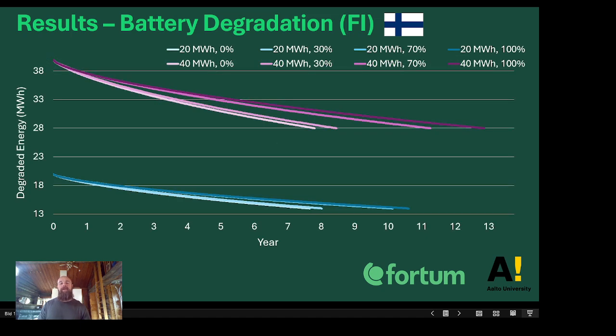This figure represents the energy capacity degradation of each scenario in Finland, and the darker the color, the more capacity is reserved for imbalance management. As can be seen, the more capacity for imbalance management, the less degradation you have and the longer lifetimes you get. For example, this line is for the 40 megawatt hour battery with 100% reserved for imbalance management, showing an operational lifetime of 13 years. All scenarios result in lifetimes of 7.5 to 13 years, and the results for NO4 and SE2 are very similar to those of Finland.